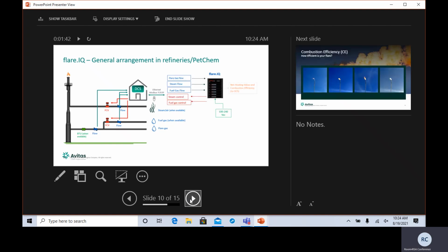So what Flare IQ does is it communicates with your DCS and provides you with optimal steam flow as well as fuel gas to balance that out, sort of riding the razor's edge when it comes to maintaining your 270 BTU and smokeless operation. And most importantly, after your process upset is done, it reduces your steam back down. Many times, during a process upset, the operators will put the steam on to get away from any black smoke, and they never turn the steam back down again.